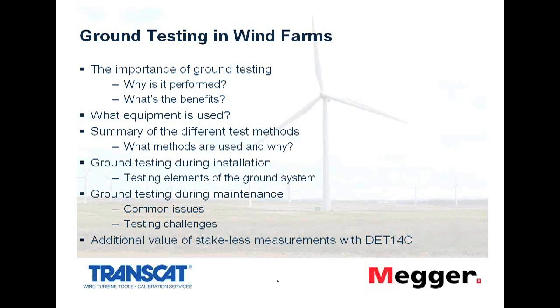and then after that we'll have a little look at the sort of ground testing that can be done during installation. In other words, breaking down the system into elements. Ground testing during maintenance follows, with a discussion on common issues and the sort of testing challenges we have. And then I'd like to finish with an additional test with one of our newer products, DET 14C, which is a stake-less measurement.